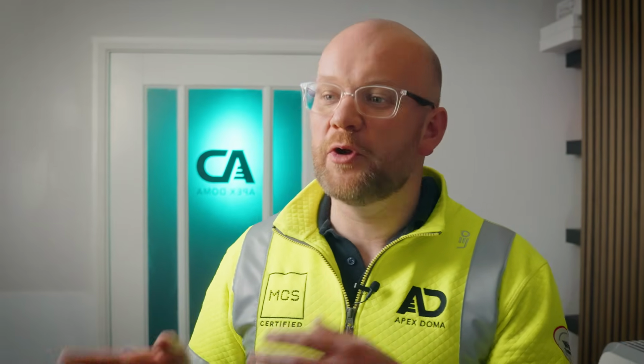I think this best practice guidance will actually become part of what we know as BS 7671, our wiring regulations, later on this year. And PAS 63100, which is this best practice guidance, basically says, look, don't install it somewhere daft. Don't put it in a loft. To be honest with you, good luck to anyone trying to install battery storage in a loft anyway. These are like best part of 100 kilos a unit. You'll end up pulling your back out in the process, so you'd probably never put that anywhere.